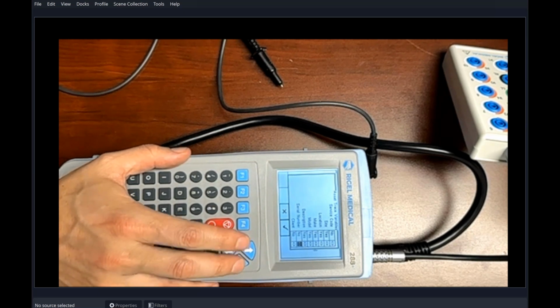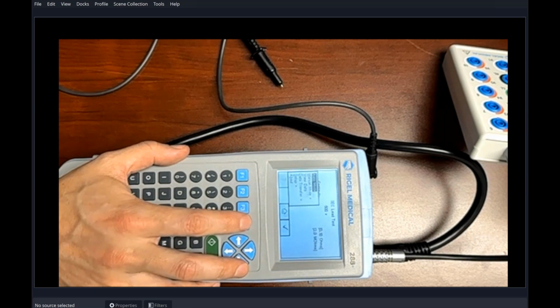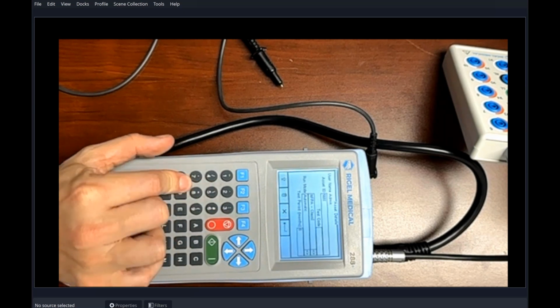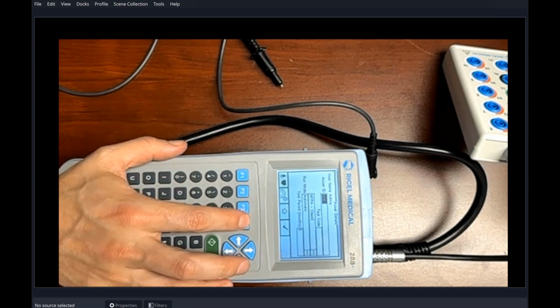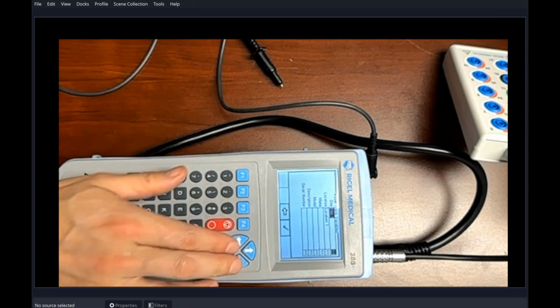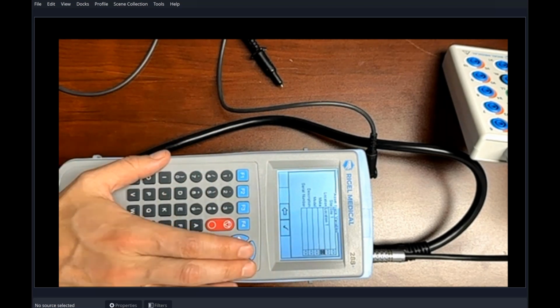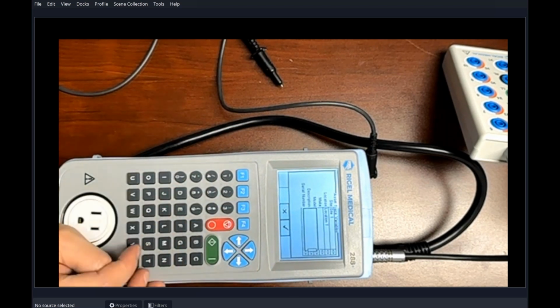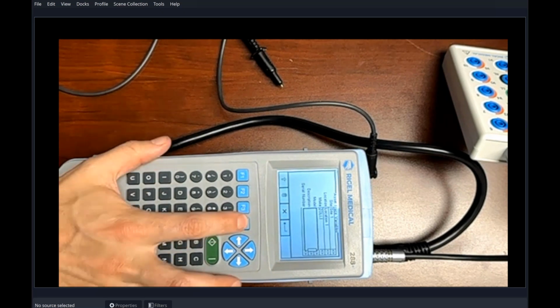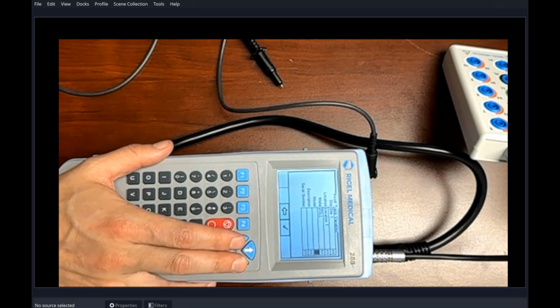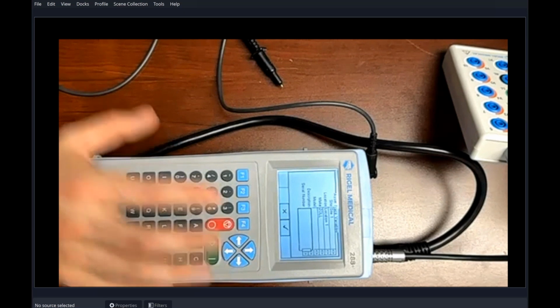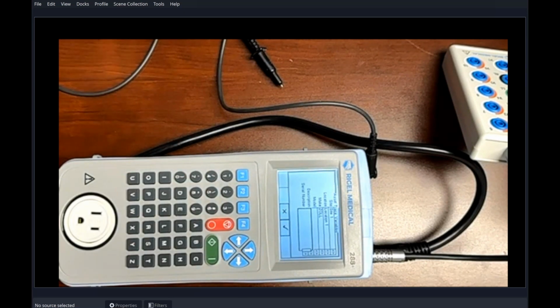If I change all those to yes, go back to automatic mode and key in the asset ID, the next stage is going to have the full list that can be input on the keypad. So make, for example, I can just go in there and add in all those asset informations before performing the test, and that will again be added onto that test report, whether it's downloaded via CSV, PDF on the application, or to the PC.